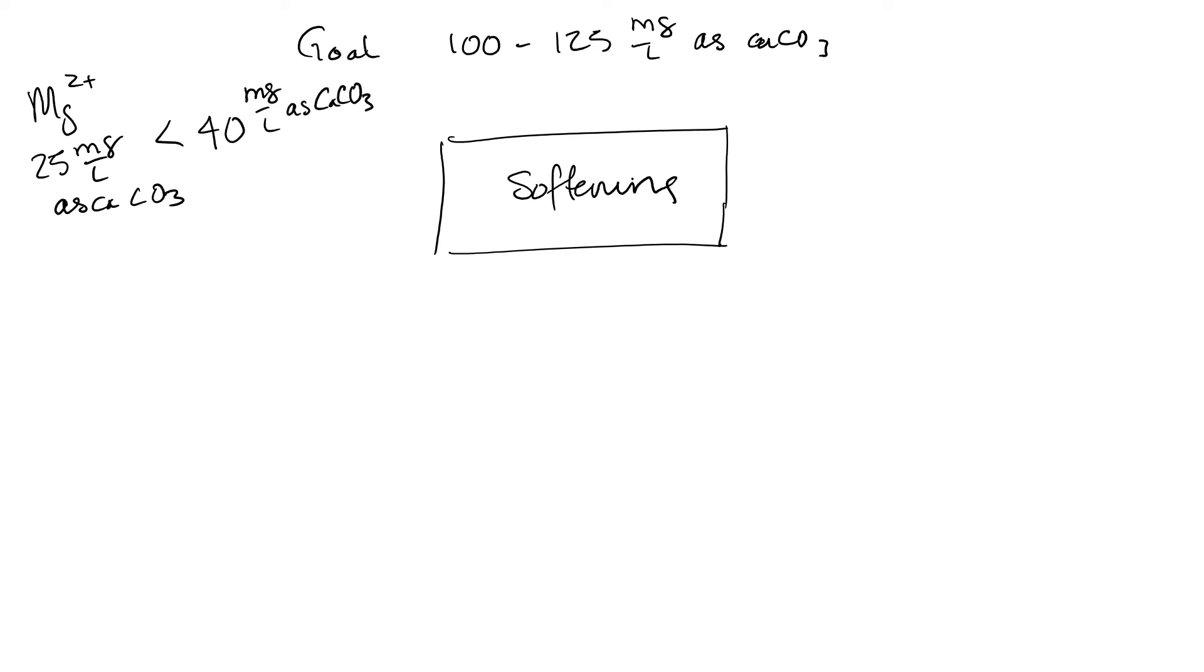Now, in the previous slide, we looked at, again, we have this goal of 100 to 125 milligrams per liter as calcium carbonate. In our softening unit, we softened to the practical limits. But think about this: our magnesium concentration is 25 milligrams per liter as calcium carbonate. That is significantly less than the 40 milligram per liter cutoff that we have based on where magnesium tends to be problematic in the distribution system.